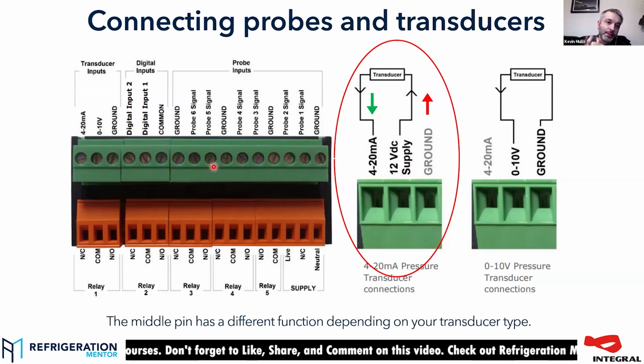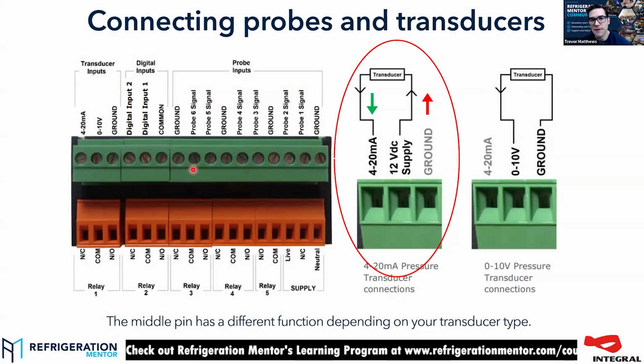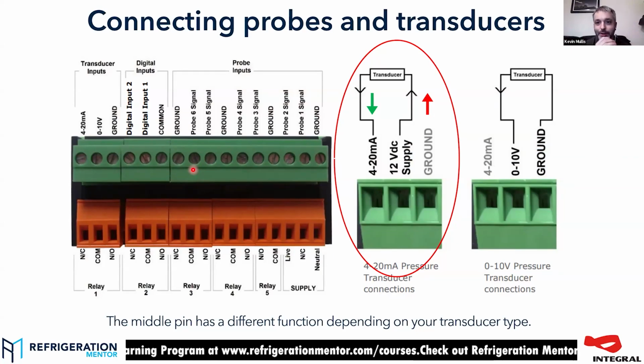Probe 5 is your defrost termination probe. Probe 6 is if you want to use a product sensor. So some of the guys on the call, I'm sure, will have seen, you can put what they call a slug probe, which isn't a little slimy thing that crawls around the fridge, but is the thing sat in a big block of polystyrene or gel that responds much more like a product.